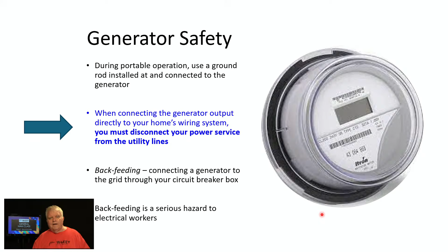Now, a lot of generator systems that are professionally installed will have this transfer switch ability built in, so you can't backfeed the lines. Because backfeeding a line is a hazard to a line person who's out there working on the lines. If you feed 120 volts from your house, that transformer can take it back up to 4,000 volts and cause a life safety hazard. So you don't want that. You want to make sure you have a visible means of disconnection or a proper transfer switch.